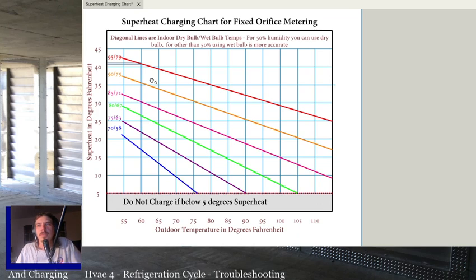But when your outdoor temperature is low, you're going to be feeding a lower pressure to the evaporator coil. Even if you've got good subcooled liquid going to that metering device, you're delivering it at a lower pressure, so it's not going to have the oomph. It's not going to have the pressure to push through that metering device. It's got to make its way through that little fixed orifice. If you've ever looked at the holes in those things, they're pretty small. So the pressure is part of what makes it feed enough refrigerant through. So anytime your outdoor temperature is lower, you're going to have higher superheat because you've got less pressure to push through the metering device, even if you've got liquid.